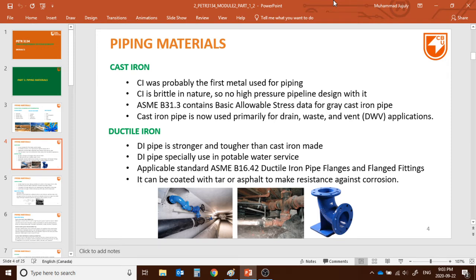Let's talk about cast iron first. Cast iron is pretty rudimentary — it's the base iron without anything added. It's the first metal used for piping, like a thousand years back, even during the Roman period. They used cast iron with lead. It got really bad design and it is highly corrosive. ASME B31.3 contains some basic allowable stress data for grey cast iron pipe, but it's not ideal because it's brittle in nature and definitely can't be used for high-pressure pipelines.